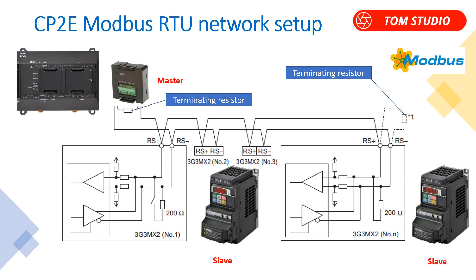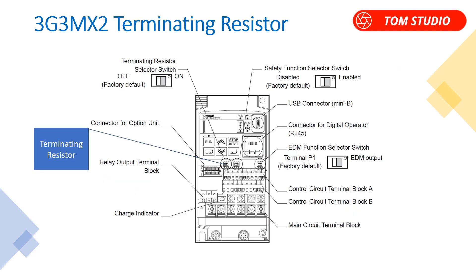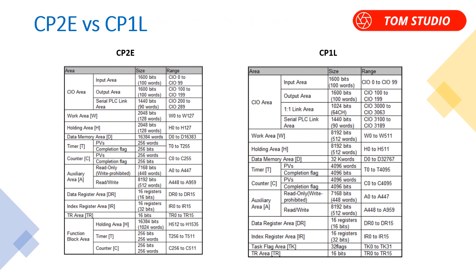To eliminate noise from the network, it is necessary to set up a terminating resistor at the first and last node devices. If the last node on the Modbus network is an Omron 3G3 MX2 VSD, you can simply turn on the terminating resistor on the VSD — no extra resistor needed. Please be aware that CP2e is quite different from CP1L. For example, CP2e W memory area is from W0 to W127, but CP1L memory area goes to W511. There are also many differences on PLC instructions, so on CP2e you cannot use existing CP1L function blocks — you must use new Modbus RTU function blocks designed for CP2e.